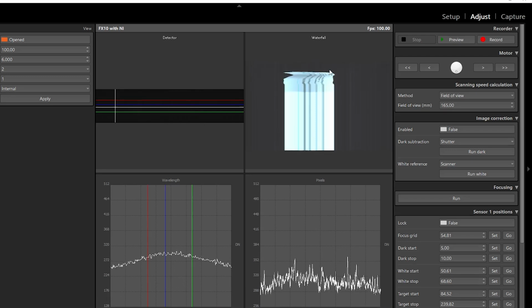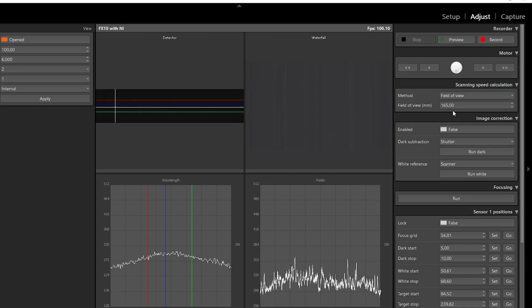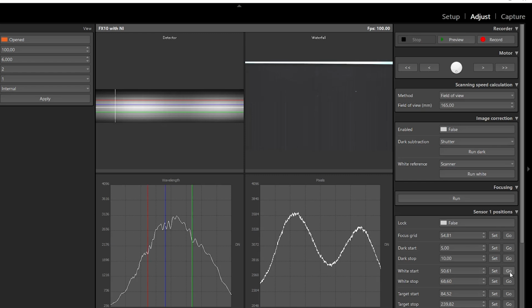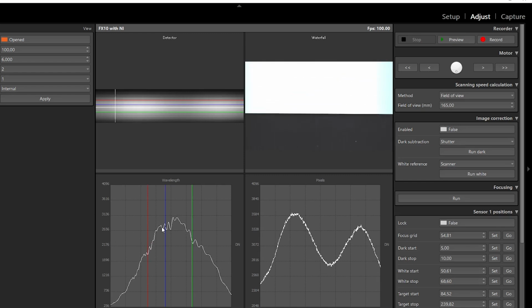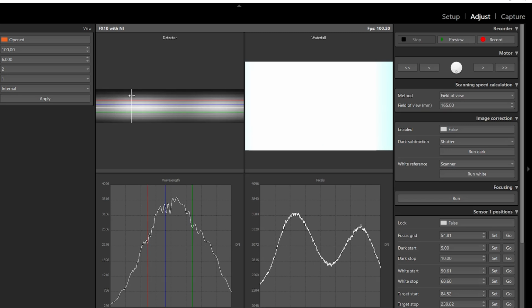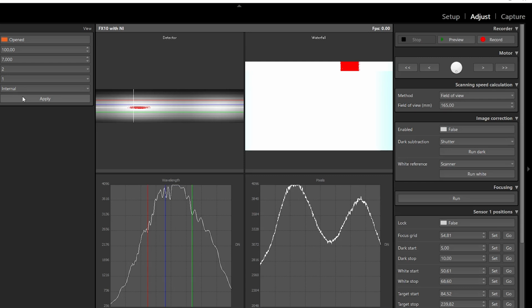Now that you have defined your field of view and you have also made the focus, the next step will be to adjust the integration time. And to do that, we move towards the white reference, we stare at it like this, and we try to have along the spectral axis a signal which is filling the well capacity but not too much of the detector. So here we are having a camera which is coding the data over 12 bits, so between 0 and 4095 in fact. And then if we put an integration time which is too high, for example here 7 milliseconds, there will be some saturation. We would like to avoid these kind of things.